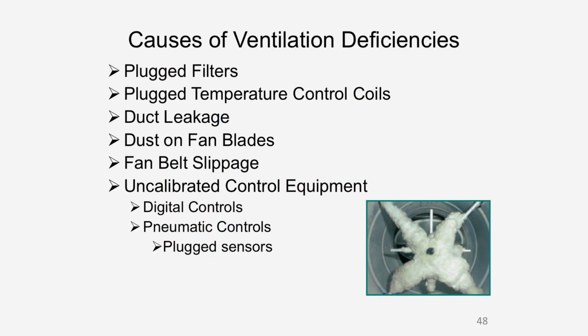The biggest problem that I see about energy misuse in hospitals is that we have deferred maintenance. We don't take care of our buildings. I've seen this worldwide. It's shocking. We have plugged filters. We have temperature control coils that are plugged, duct leakage. Didn't put it together right. Oh, boy. You see dust on fan blades, which really slows the efficiency down, and they don't make sure that the fan belts aren't slipping on top of that. They don't calibrate. We don't calibrate our equipment. And what you see that's all covered with fuzz there is a sensing device called a pitot tube that is being plugged with lint in hospitals.